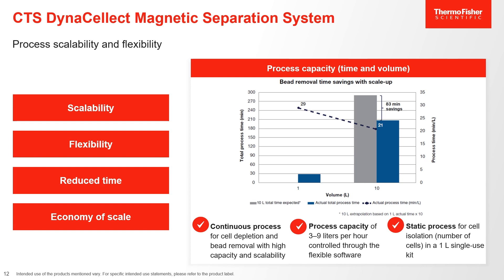Aside from a gentle, efficient isolation of T-cells, two of the other significant advantages of the DynaCellect system are its scalability and processing times. When running a one-liter culture through the bead removal protocol at the standard speed of 50 milliliters per minute, total processing time will be around 29 minutes, which includes the material loading and final recovery steps. When processing larger volumes, it would be assumed that every liter above one would require the same amount of time. However, due to the continuous flow through the serpentine bag, there is no need for redundant beginning and ending steps. When compared to a single liter, a 10-liter culture can be processed at one liter every 21 minutes, resulting in up to a 30% time savings at larger volume, utilizing only a single kit with no need for mid-run user intervention. Having such clear expectations going into a run makes purchasing and allocating resources much easier, especially when operating at a manufacturing capacity.